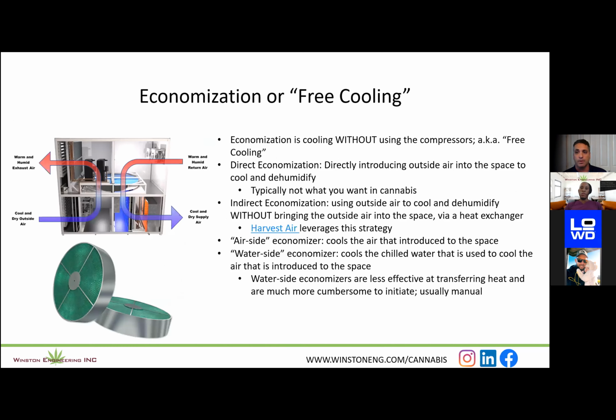All right, so going a little bit deeper, this is looking at economization or free cooling, okay? So economization is cooling without using the compressors. Remember, the compressors use 80% of the energy in your system, right? So free cooling. There's various types of economization. There's what's called direct economization. So that effectively is using the outside air and bringing it into the space as if you're opening the window to cool and dehumidify, right? So you don't have any losses of your heat transfer when doing that because you're not running it through a heat exchanger. But you are bringing in outside air and all that comes with it, all the pests, pathogens, temp swings, humidity swings, you know, the craziness with your climate, not exactly what you're looking for in the space.